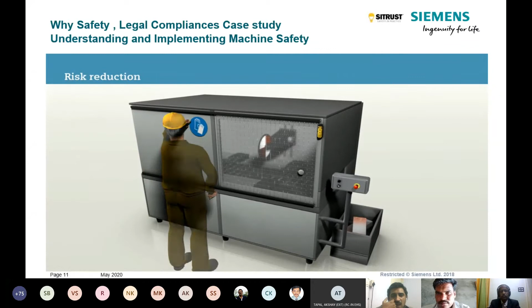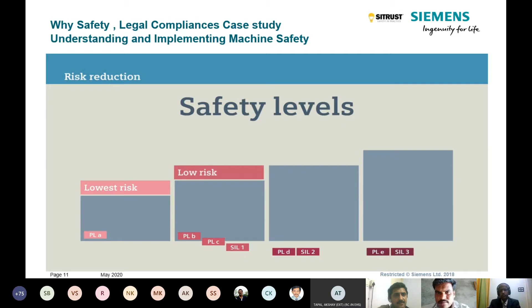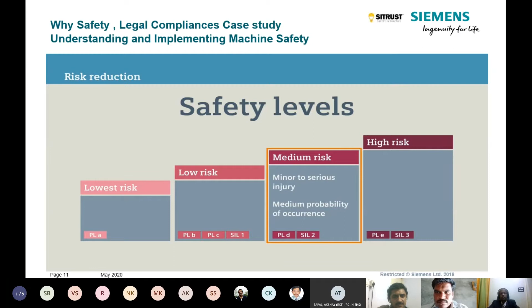Now determine, depending on the original risk, a certain safety level. You can apply 2 different standards. The ISO 13849 Part 1 standard defines the performance level PL in the gradations A to E. On the other hand, the IEC 62061 standard uses the term Safety Integrity Level, short SIL 1, SIL 2, and SIL 3. Here, to clarify, is a graphic comparison of the 2 levels in 4 different risk categories. For the safety door on our machine, the performance level PL d, or the safety integrity level SIL 2, is determined.